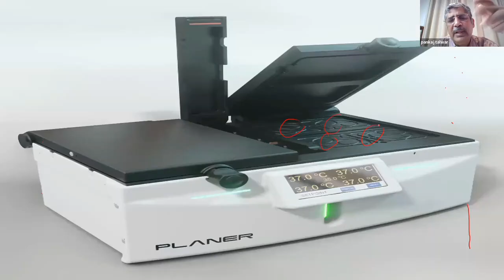But once you open it, the temperature and gas will be lost very quickly. So in case we keep only 1 patient per chamber, we have better control. That's the main disadvantage, but they come cheaper and give you chamber 1, chamber 2, with temperature shown here. And they are dry gas incubators and they work without humidification. This is my favorite benchtop incubator, called Mink. Here you can see the humidification flask, which is giving humidity to the chambers, and you can do 4 patients. But normally I don't put more than 2 patients, 2 here and 2 here. That's all I do. So they are called dry gas incubators.